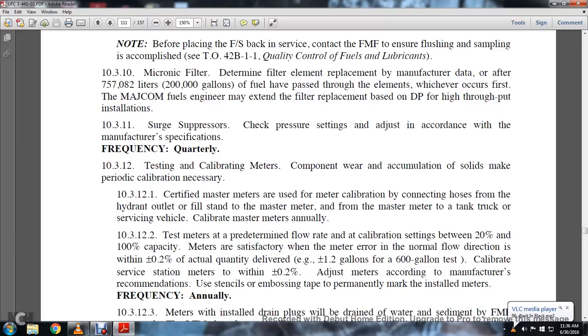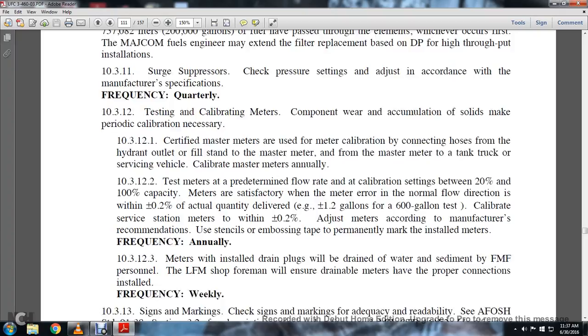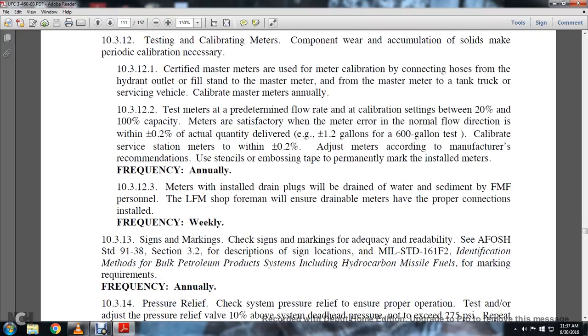Calibrate the service station meters to within plus or minus 0.2%, adjusting the meters according to the manufacturer's recommendation. Use a stencil, embossing tape, or permanent marking on the installed meters. Frequency: annually. Alright, continuing with meters. Meters with installed drain plugs will be drained of water and sediment with the fuel maintenance flight personnel. The liquid fuels maintenance (LFM) shop foreman will ensure the draining of meters from the proper connections.